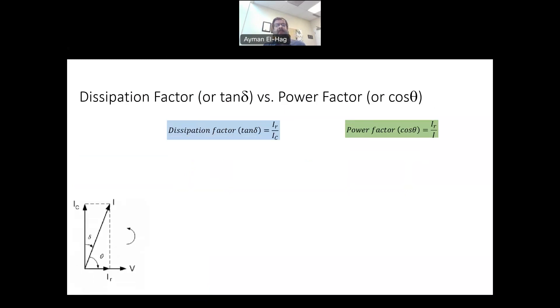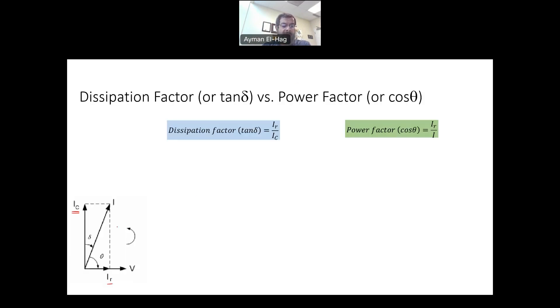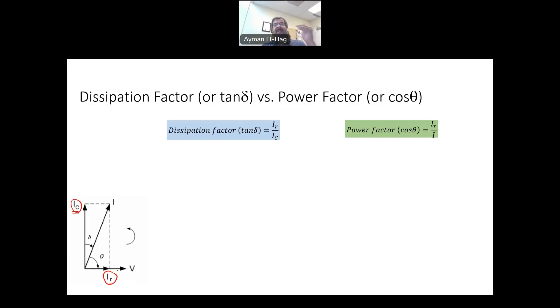To understand what the dissipation factor and power factor are, consider this triangle, which shows voltage versus currents. We have IC, the capacitive current, which is 90 degrees with the voltage. We have IR, which is the resistive current. And we have I, which is the total current. The dissipation factor is the ratio between the resistive current and the capacitive current. The power factor, on the other hand, is the resistive current divided by the total current.